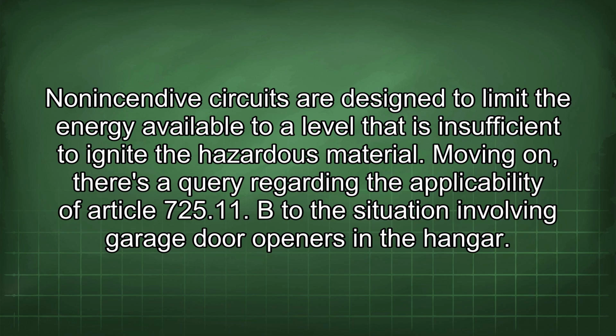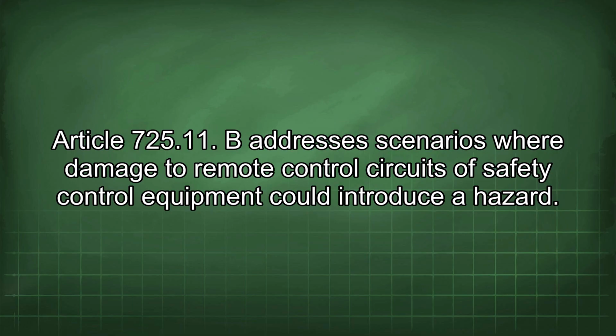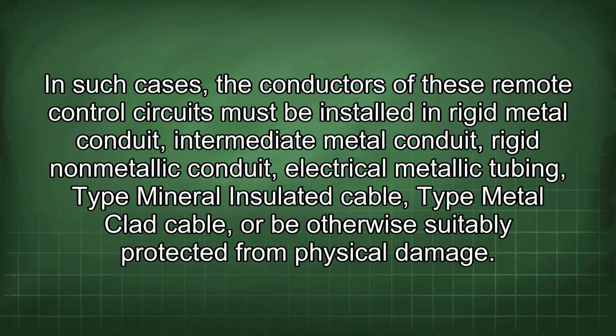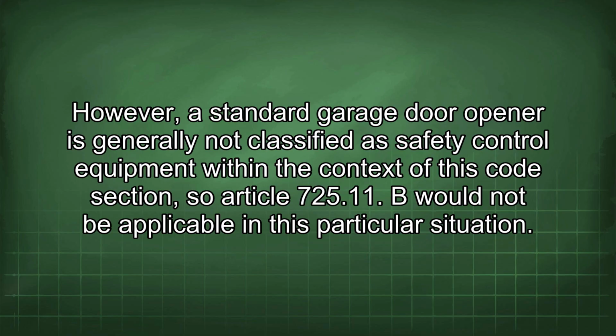Moving on, there's a query regarding the applicability of Article 725.11(B) to the situation involving garage door openers in the hangar. Article 725.11(B) addresses scenarios where damage to remote control circuits of safety control equipment could introduce a hazard. In such cases, the conductors of these remote control circuits must be installed in rigid metal conduit, intermediate metal conduit, rigid non-metallic conduit, electrical metallic tubing, type mineral insulated cable, type metal clad cable, or be otherwise suitably protected from physical damage. However, a standard garage door opener is generally not classified as safety control equipment within the context of this code section, so Article 725.11(B) would not be applicable in this particular situation.